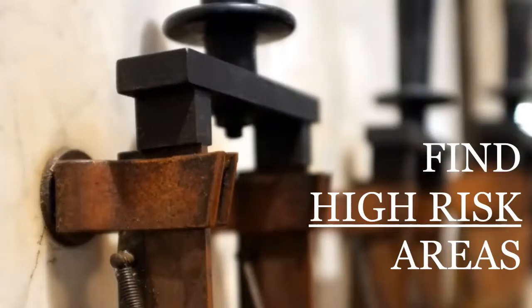It's knowing exactly what you need for PPE, and also being able to identify those high risk areas, which can then be mitigated. That's where the engineering controls come in. Like we were talking about earlier, you could maybe change fuse sizes, or start to work with the system and get those levels down to a reasonable number.